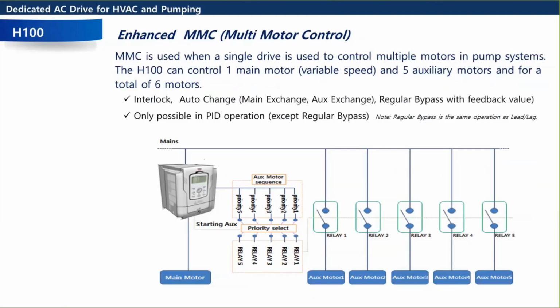So here's the load sharing that I saw somebody asked a question about. We have two different options or flavors for load sharing. First is this multiple motor control. Multiple motor control is commonly called a contactor lag. So you have one drive which is running a main motor, and that's going to be a variable speed one because that's running off the drive. And then we have those 5 relays that we could run to motor starters for across-the-line starts on auxiliary motors. So we could have up to 6 motors running off of one drive. One of them is going to be running variable speed, and the other 5 are going to be running across-the-line starts based on these relays, giving them a run command or closing a coil or whatever. Okay, so we have a few people that use this.